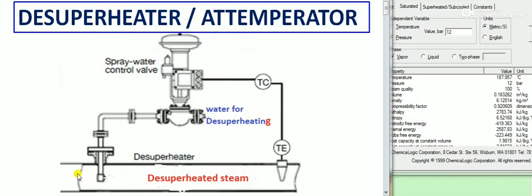We have the superheated steam in the pipeline, so we have the de-superheater connections in the pipeline. In the de-superheater, what will happen? The steam will pass through and water will pass through the pipe, and it will get sprayed or atomized. If we directly add water into the steam in the full pipe bore, definitely water hammering will occur, right? To avoid that, we want to make it into droplets. Water should form droplets, so it easily mixes into the steam and reduces the steam temperature.